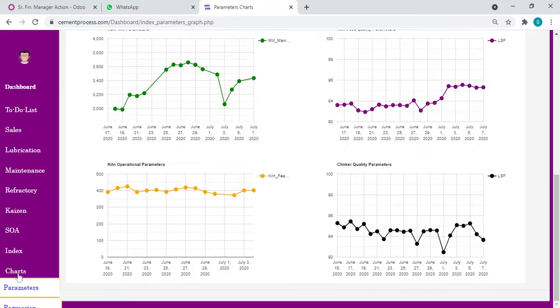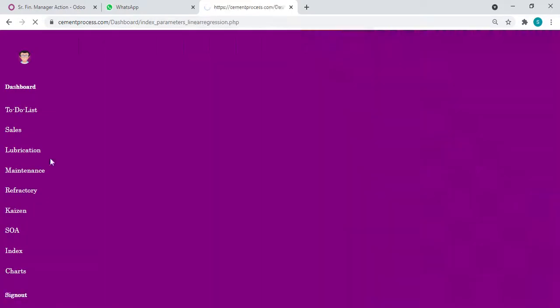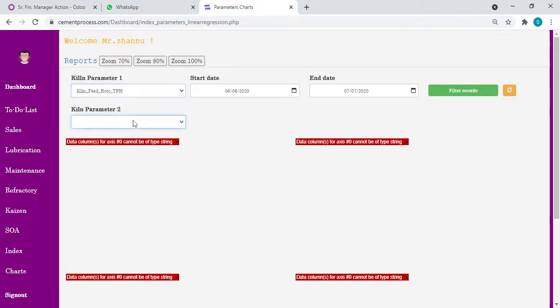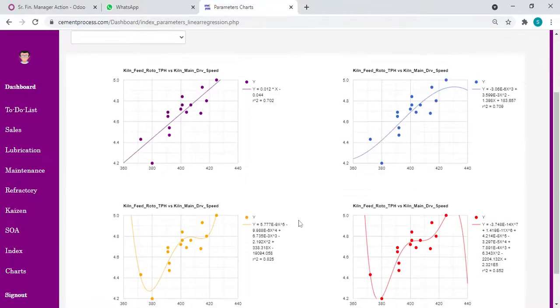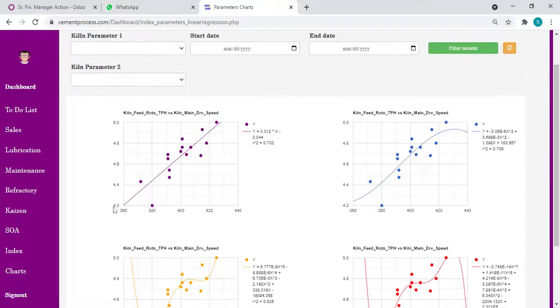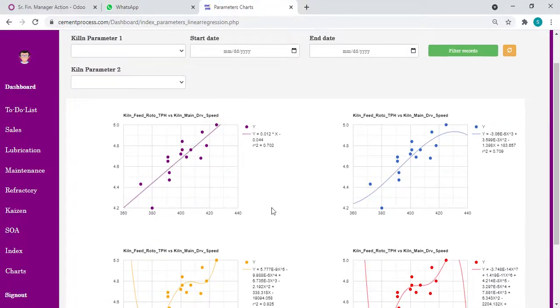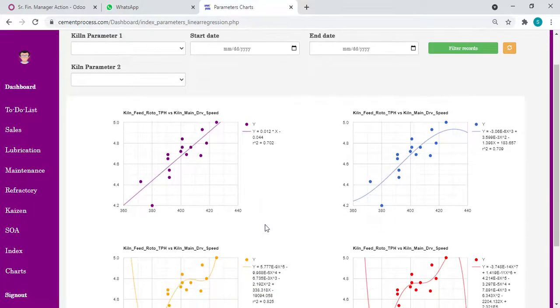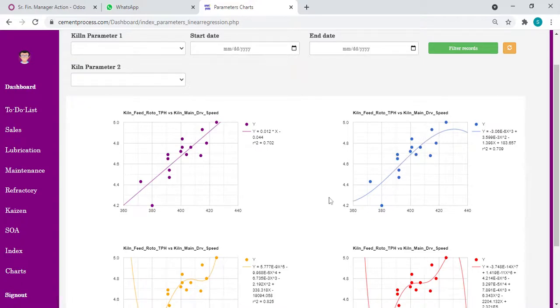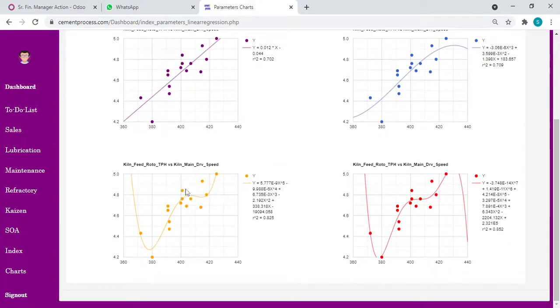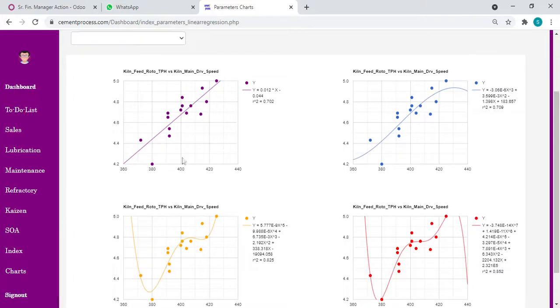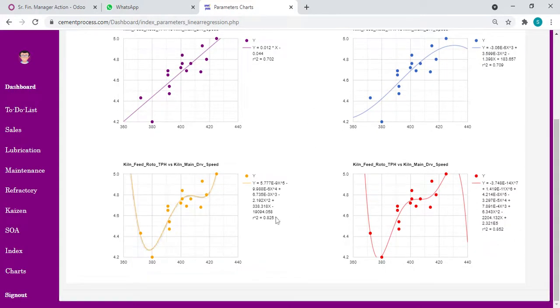Now coming to regressions. We can compare any parameter with any parameter. We can take two parameters and see what is the relation. Let's start with kiln feed versus kiln speed. Now we filter the records. See, here you will see the graphs, what is the correlation. You can see kiln RPM equals 0.012 into kiln feed minus 0.044. I put linear interpolation, polynomial third degree, polynomial fifth degree, and polynomial seventh degree.